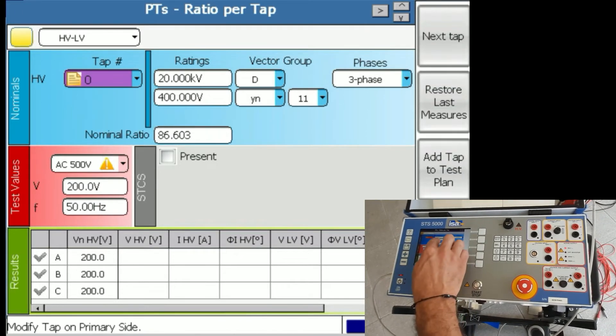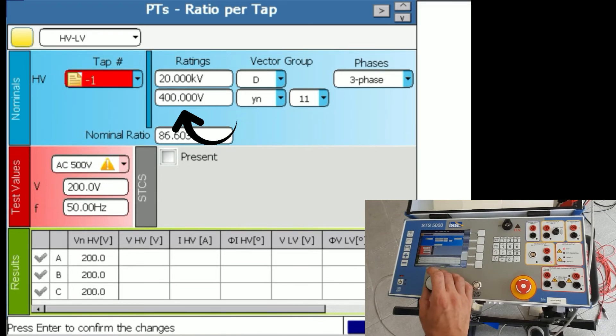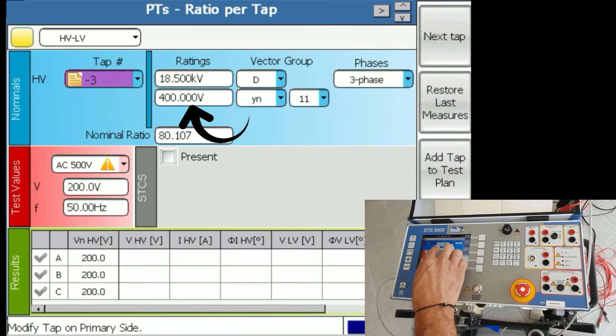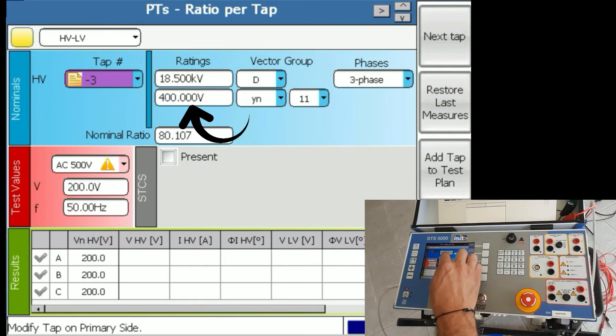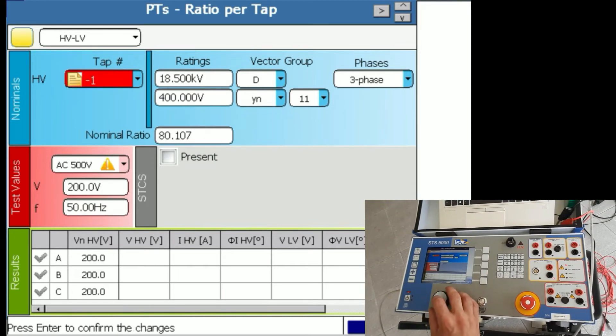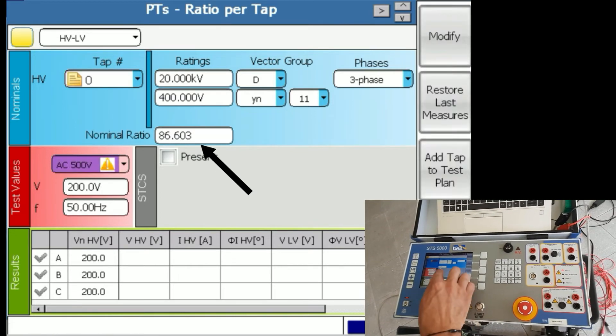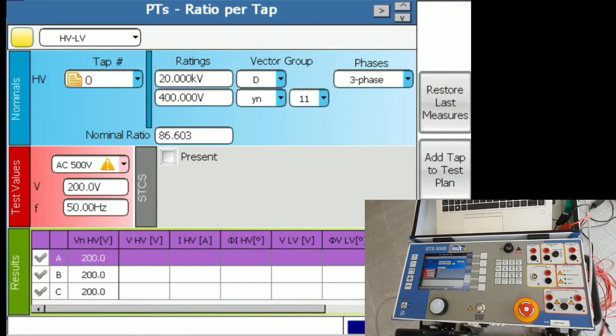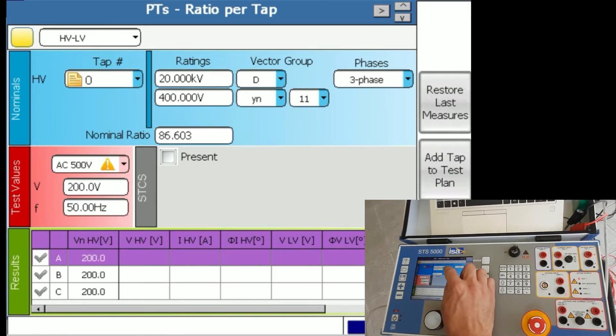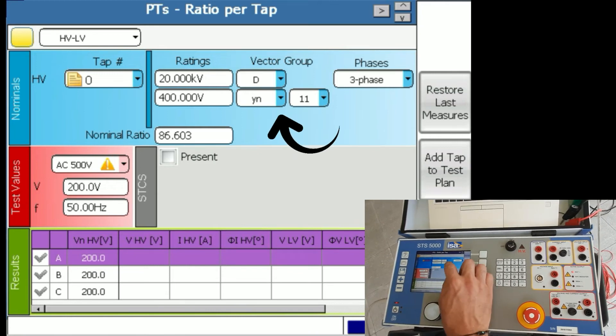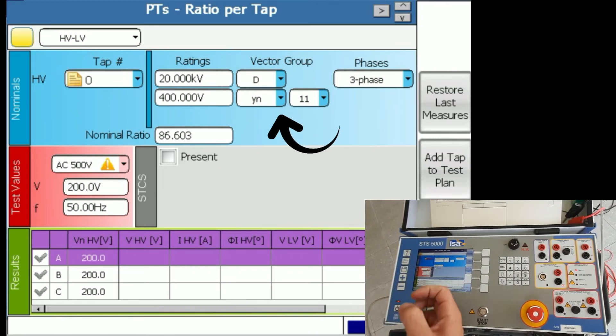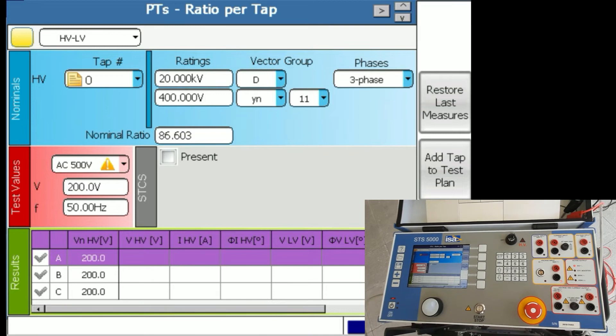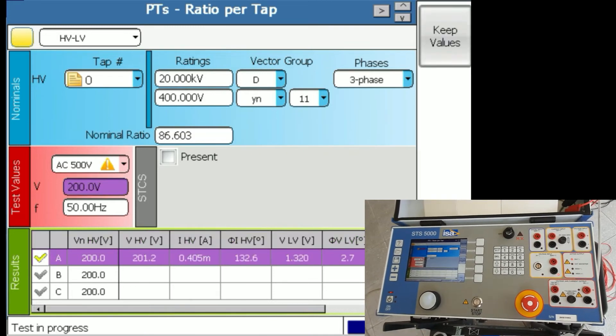It's actually in position zero and you can see 20 kilovolts to 400 volts. If I put it in position minus three, it will be 18.5 to 400. The same way, the ratio changes. Now it's 80, and in position zero it is 86.6. So this is the result we're looking for, vector group Dyn11, which was transcribed, copied from the nominal values.